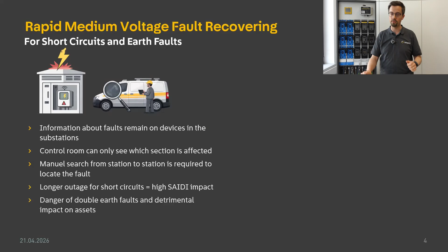And so being able to address these more quickly is really important. And one final point is also the earth faults. So earth faults can happen. The first earth fault isn't actually all that critical, but it represents a danger because as soon as the second earth fault occurs, that's particularly dangerous. And so being able to know that the first one has happened and where it might be is also very important for safety. So that's the kind of situation where we're at the moment.